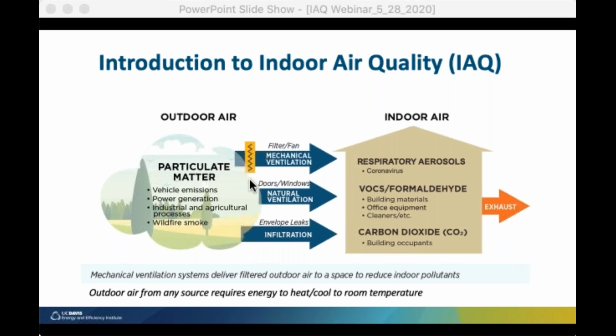There are three ways outside air can make it to indoor air. One is through mechanical ventilation. The other is natural ventilation, through opening doors and windows, and also air can leak from outdoors to indoors through cracks in the building envelope. Among these three routes, mechanical ventilation has the greatest potential as a means to control indoor air pollutants, because air can be filtered before it enters indoors. It can also be controlled using a fan and programmable thermostats.